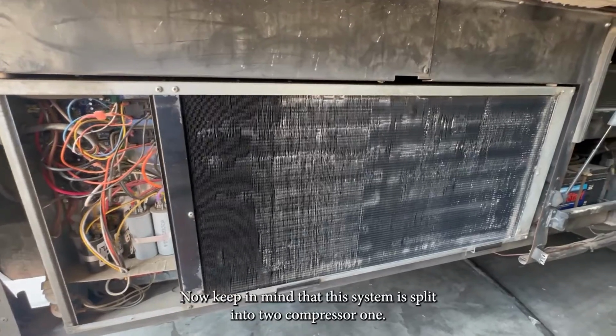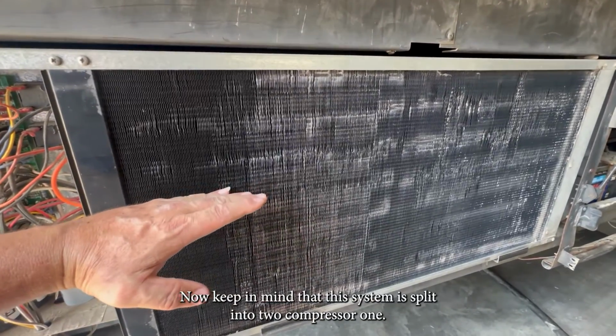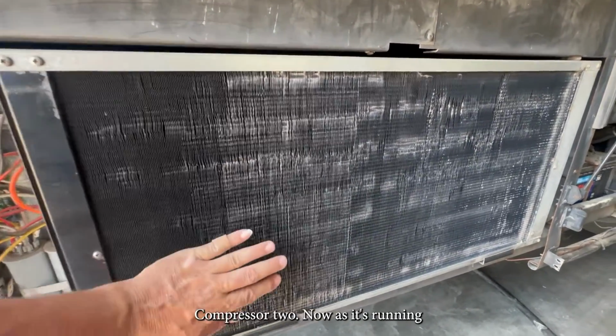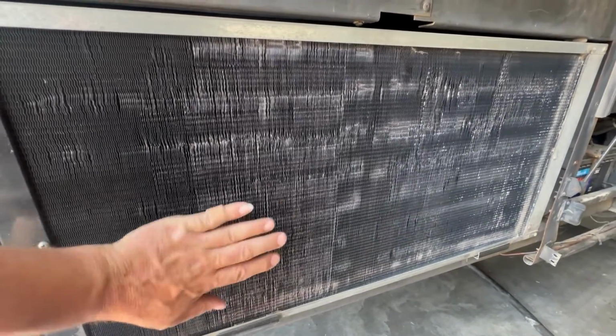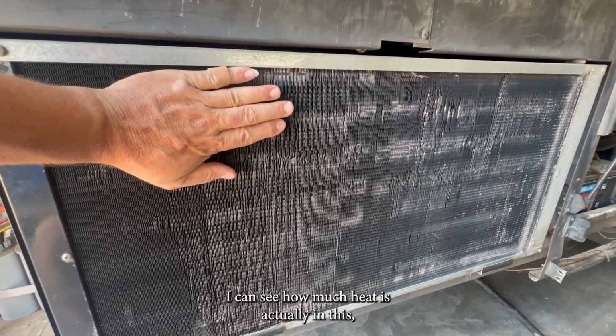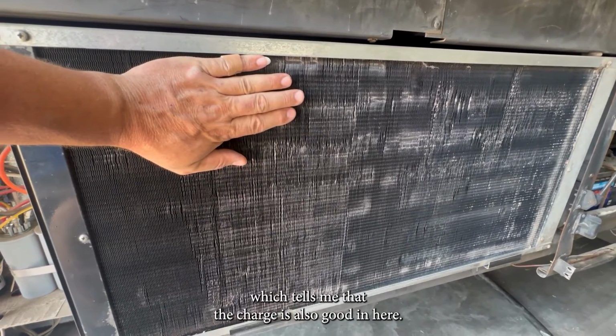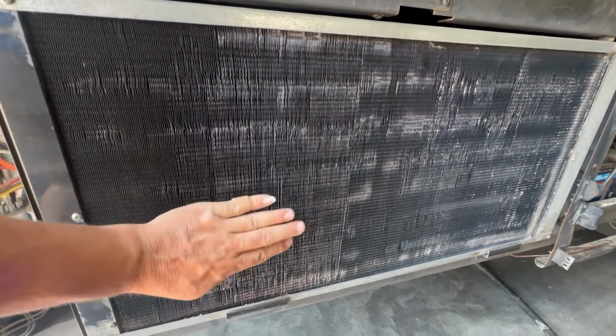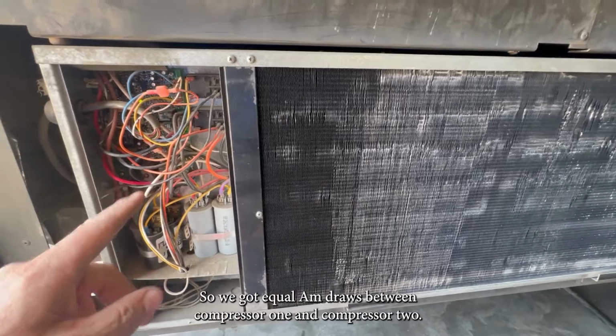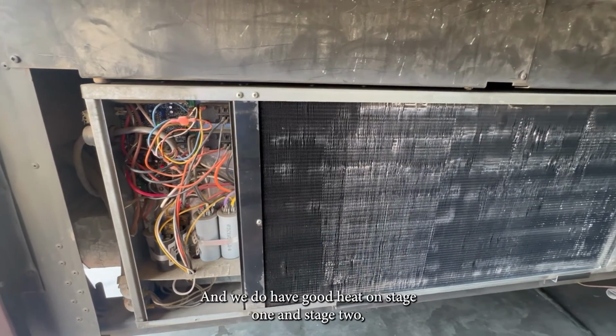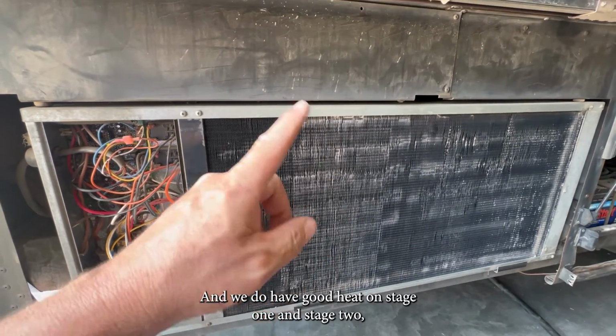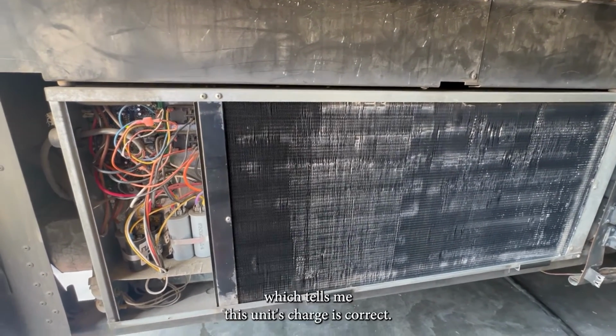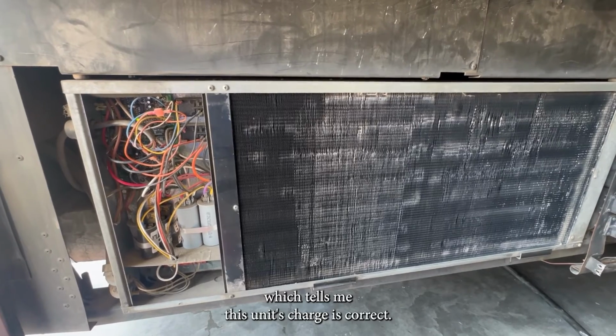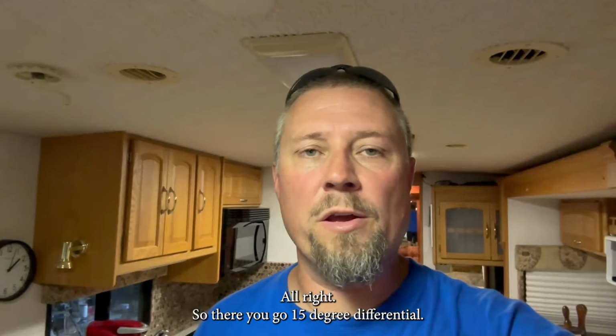Now keep in mind that this system is split in two, compressor 1, compressor 2. As it's running, I can feel how much heat is actually in this, which tells me that the charge is also good in here. So we've got equal amp draws between compressor 1 and compressor 2, and we do have good heat on stage 1 and stage 2, which tells me this unit's charge is correct. All right, so there you go.